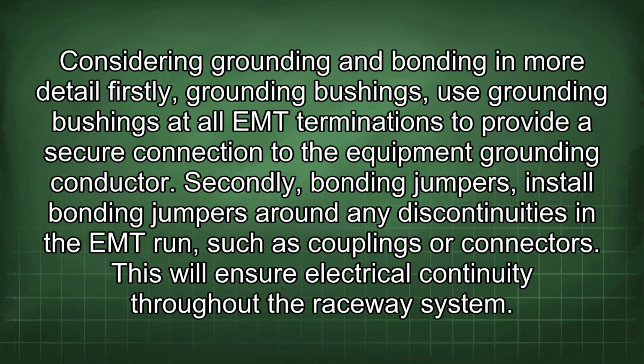Considering grounding and bonding in more detail. Firstly, grounding bushings. Use grounding bushings at all EMT terminations to provide a secure connection to the equipment grounding conductor. Secondly, bonding jumpers. Install bonding jumpers around any discontinuities in the EMT run, such as couplings or connectors. This will ensure electrical continuity throughout the raceway system.